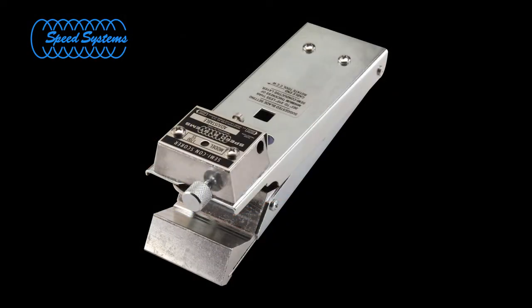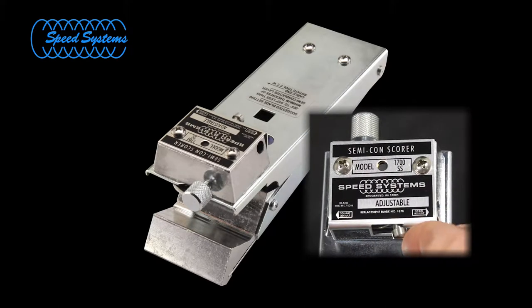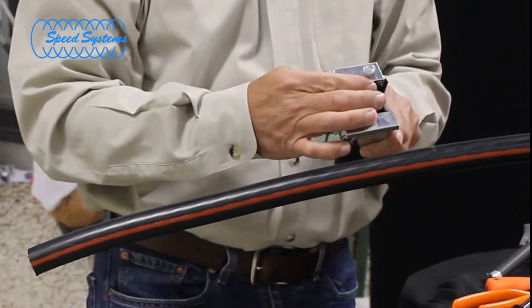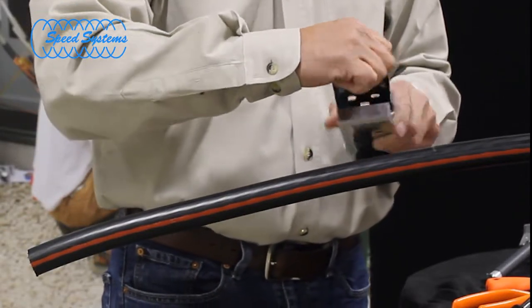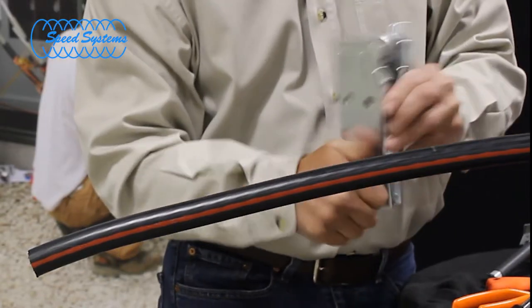Use the 1700SS to make a square cut in the outer jacket at the mark. Make sure the blade is in the square cut position. Open the jaws by turning the knob counterclockwise until the tool can be positioned on the cable. Set the blade depth so the blade does not touch any of the neutrals.